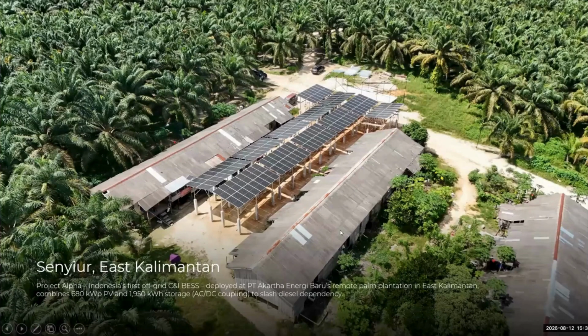And this one was installed last year. It is installed in Indonesia, in Kalimantan, and it is for a purely off-grid application. The customer installed PV panels with the Sungrow PV inverter combined with the C&I BESS for daily self-consumption. And when the solar energy is not enough or the BESS has a low SOC, then the EMS will send the order to the diesel generator, and the generator will act as a backup of the BESS.